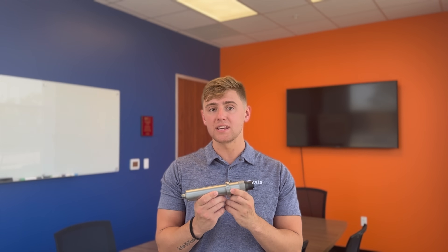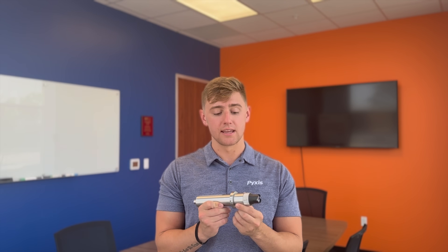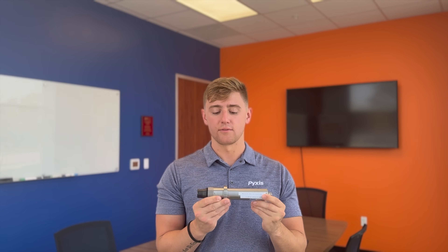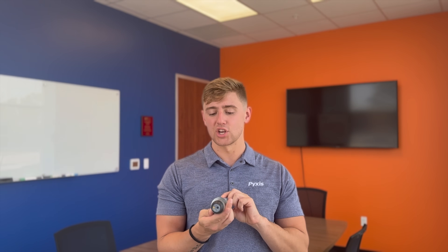A big reason is the ST765 itself. This is an oxidizer plus pH and temperature sensor. It is non-wet chemistry — no electrolyte solution, no reagents — very cost effective to the water treater, and minimal maintenance. It offers a replaceable sensor head, bare gold electrochemical technology to measure for the oxidizer, a pH bubble, and a platinum disc.